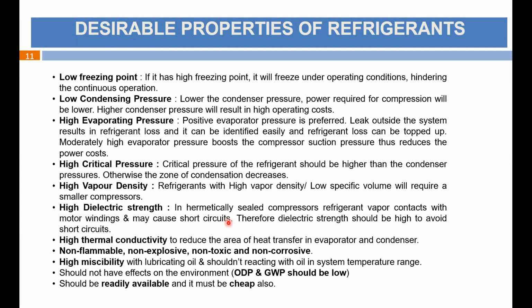Also, it should be non-flammable, non-explosive, non-toxic, non-corrosive. High miscibility with the lubricating oil, it should not react with the oil in the system operating range, and it should not have an effect on the environment, ozone depletion as well as global warming. So both ODP and GWP should be low, and it should be readily available and price competitive. So these are the ideal, desirable properties of a refrigerant.